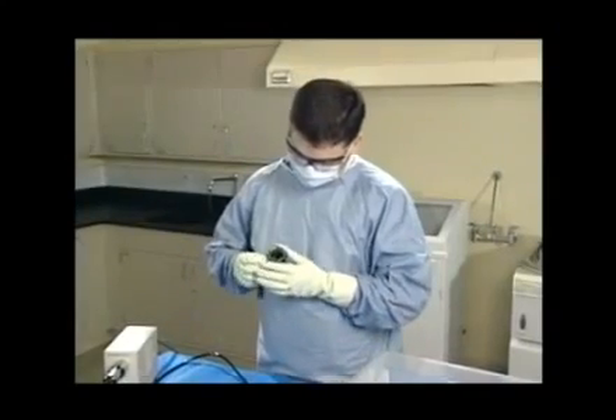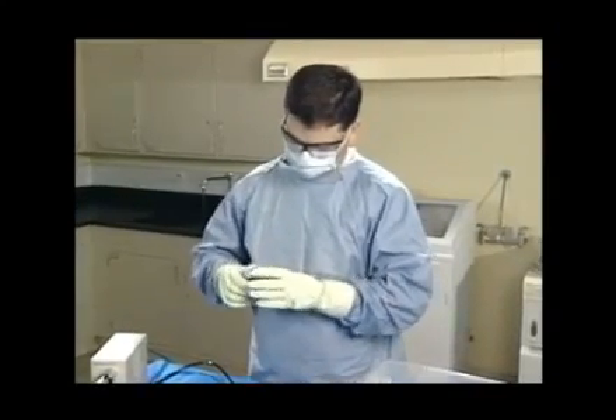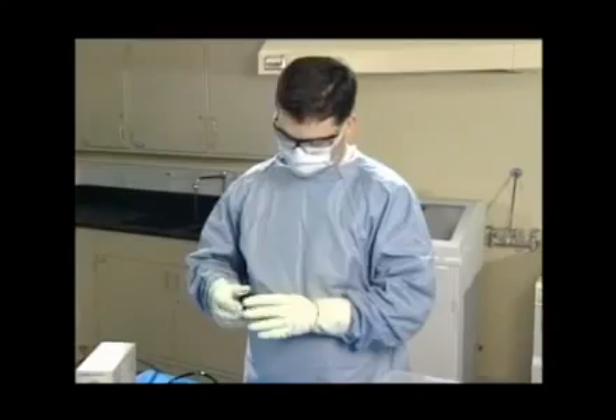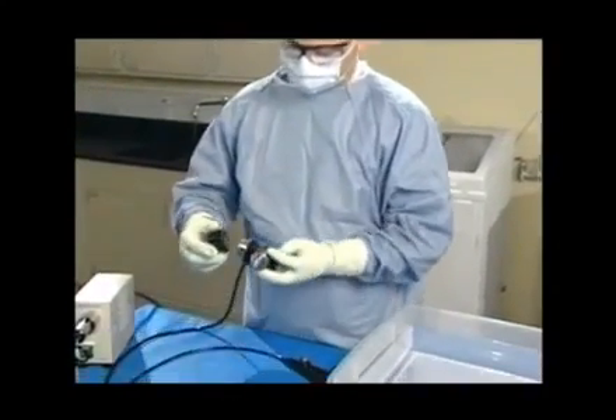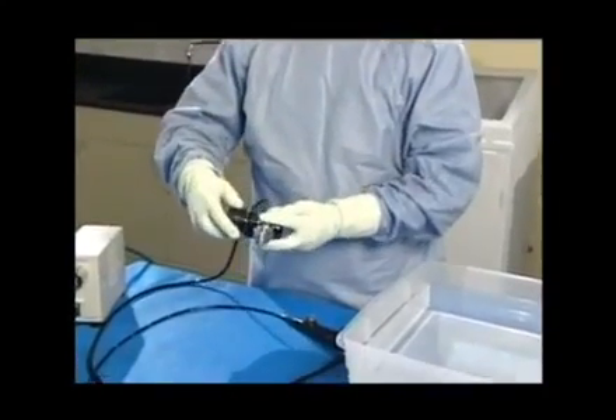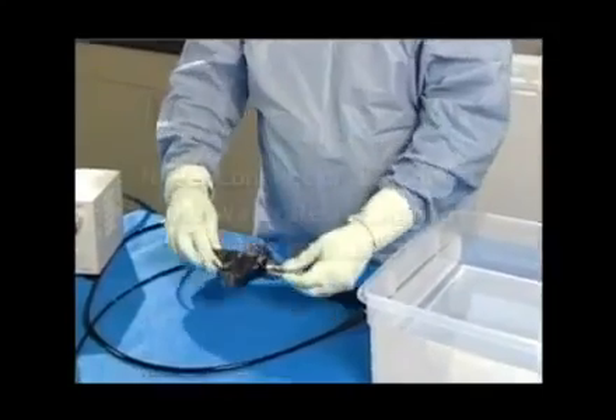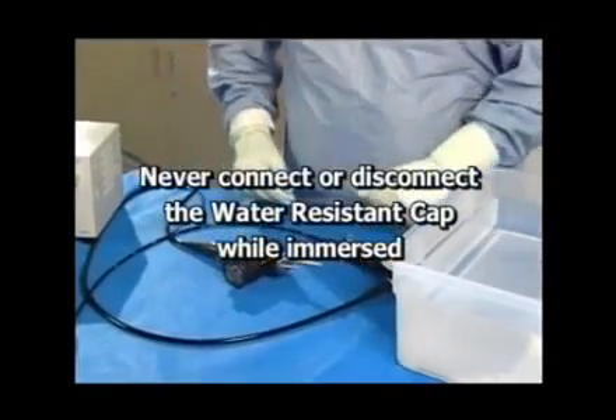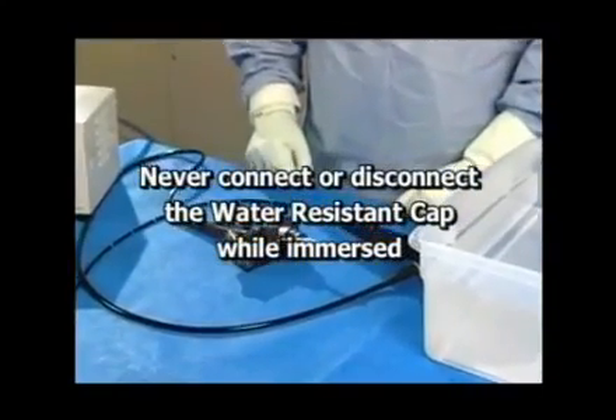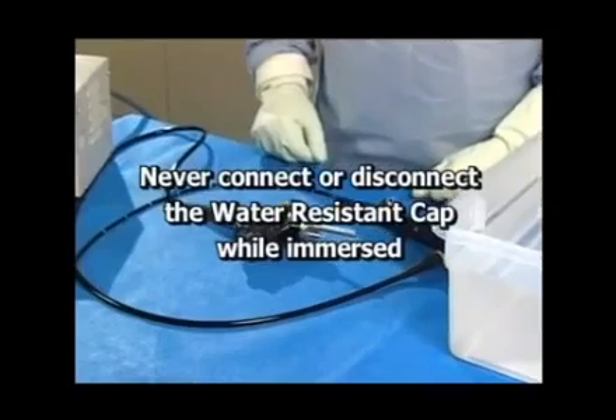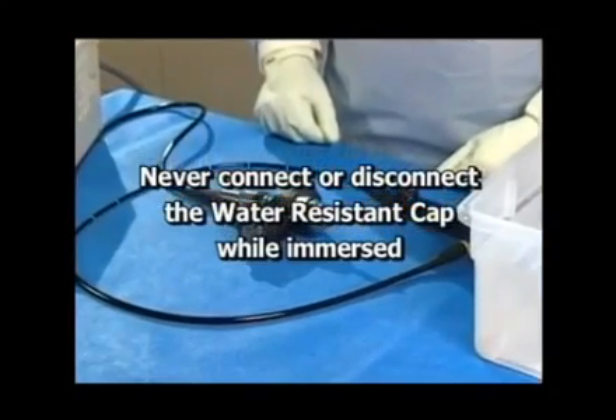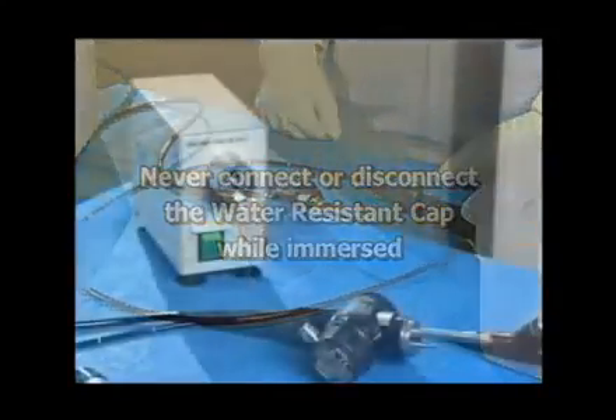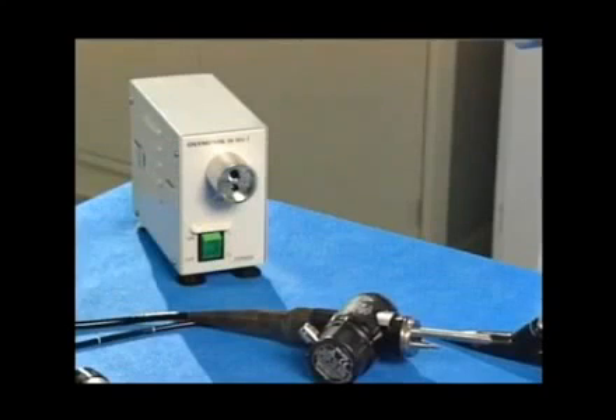The following steps should be performed prior to immersing your bronchoscope in any fluid. Visually inspect the water-resistant cap for damage. If it is damaged or wet, use another cap. Attach the water-resistant cap to the bronchoscope. Remember, never connect or disconnect the water-resistant cap while the cap or the bronchoscope is immersed. Doing so will damage the bronchoscope. Now we are ready to proceed with leakage testing.